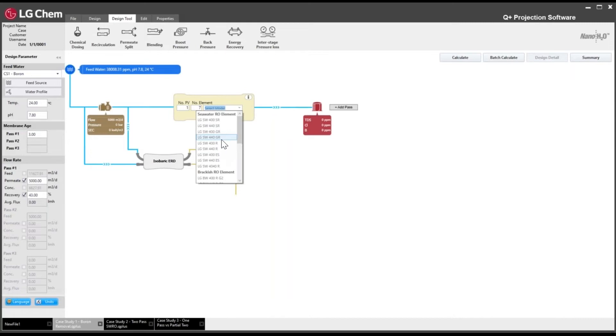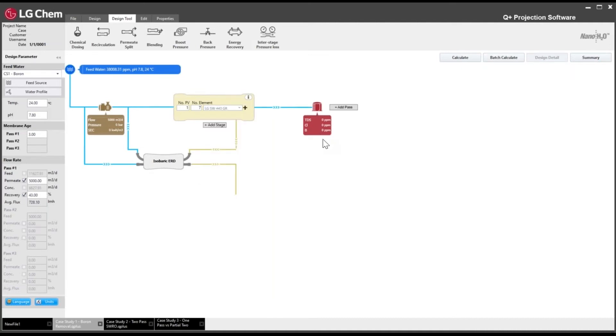The R membrane has the highest flow, GR has intermediate flow, and SR has the lowest flow — meaning SR gives the best permeate quality and R gives the worst quality but at lower feed pressure. Let's start with the intermediate GR membrane, and see if we can meet permeate quality comfortably. If we can meet it easily, we might switch to a looser membrane; if the permeate quality is insufficient, we may switch to the tighter SR membrane.